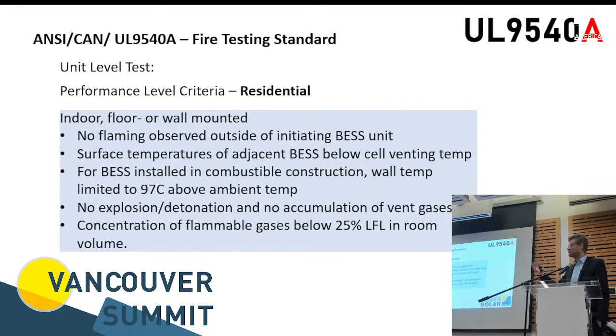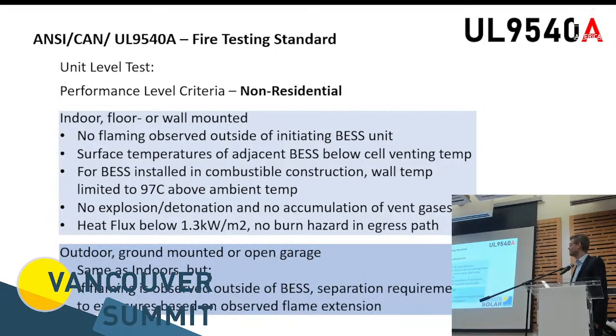And the radiation, the heat radiation from that system to walls or the environment, that walls beside it cannot exceed a certain temperature, so that you're not igniting, for example, some studs in your basement or in your room that are wooden, and nothing is going up in flames there. And you cannot have any explosion or accumulating of gases that can then lead to an explosion afterwards. That's also the last element, that the flammable gases need to be below a certain level. For outdoor systems, it's pretty much the same, but you have different separation requirements if the manufacturer has an issue with his design, that flames are actually observed. And then, of course, it cannot be put in a building.